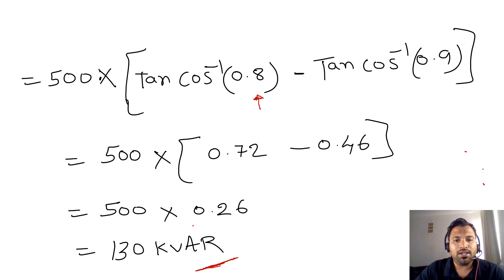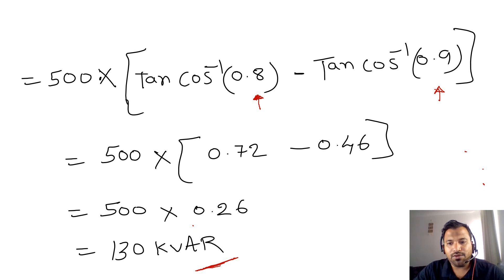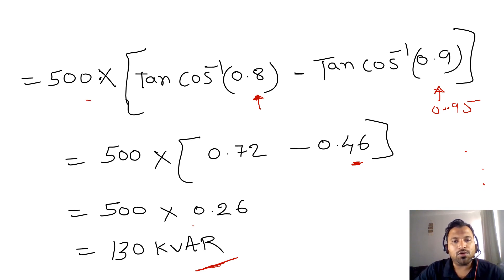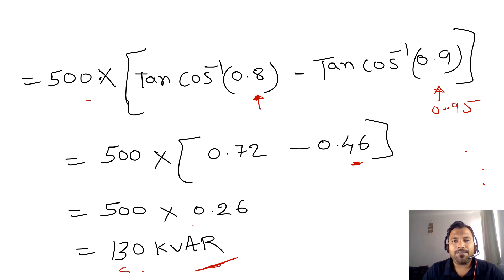For example, in a DEWA or similar exam, if they require a power factor of 0.95, this multiplying factor will change. So remember the formula: kVAR = Load × [tan(cos⁻¹ of old power factor) − tan(cos⁻¹ of new power factor)]. If you know this formula, it is very easy to find out the total kVAR required. That completes Step 1.